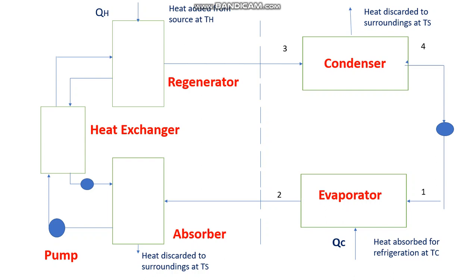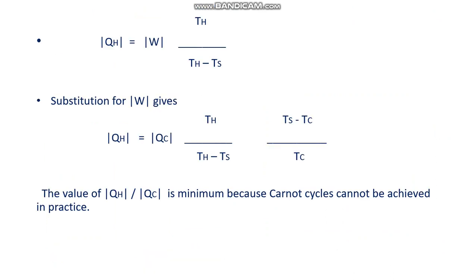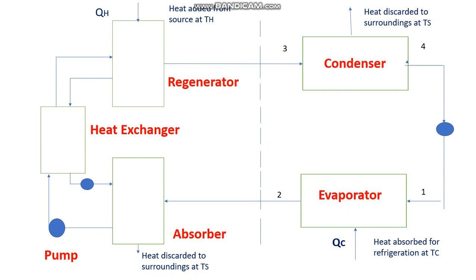From this we can write the equations: qh = w × [Th / (Th − Ts)]. Substituting for w gives: qh = qc × [Th / (Th − Ts)] × [(Ts − Tc) / Tc]. This value of qh / qc is a minimum because Carnot cycles cannot be achieved in practice. Using these equations we can evaluate qh and qc for the absorption refrigeration system.